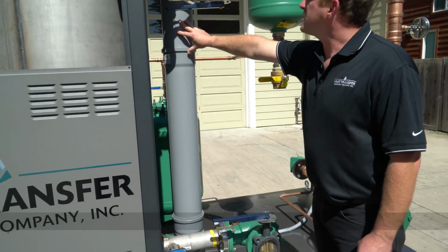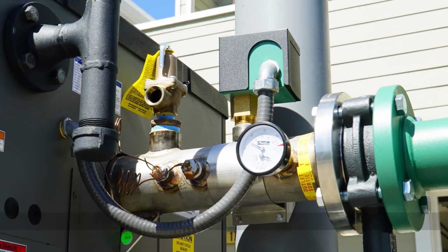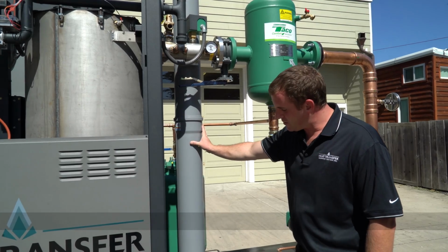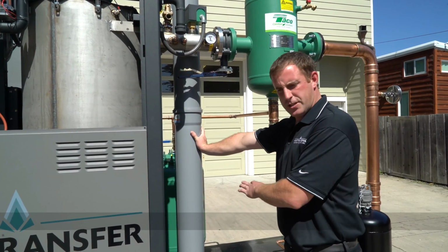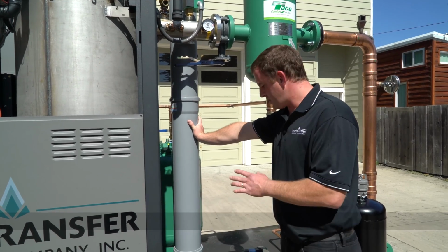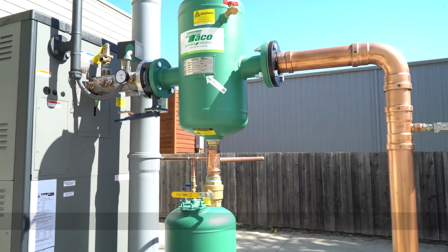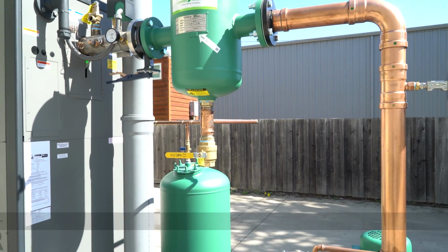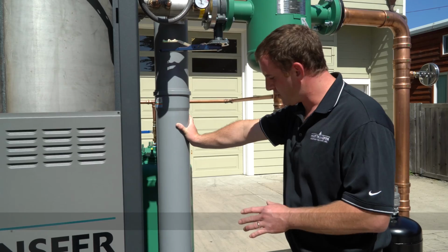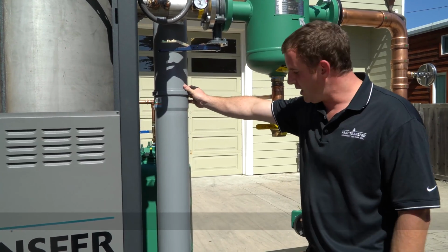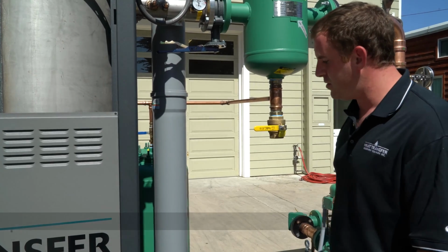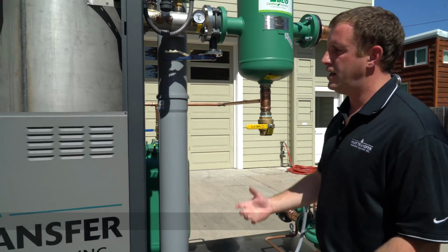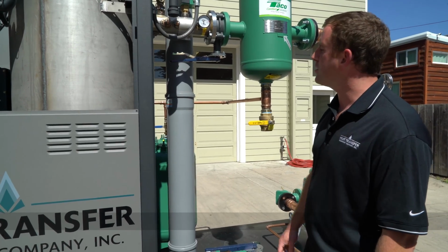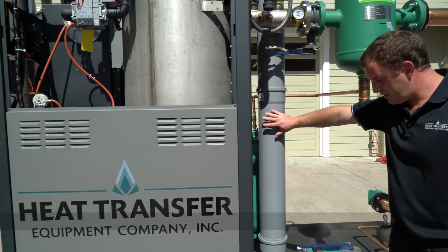On this particular boiler is Raypak's outdoor vent termination kit. It comes with polypropylene Centrotherm venting material, adapter piece, two 36-inch lengths, T termination, which we don't have mounted for shipping purposes. Built into this is a flue temperature sensor. When you start the boiler up, you have to program the flue material, and it will limit the boiler based on what the flue material selected is. Obviously, certain non-metallic venting materials like PVC or CPVC have lower temperature thresholds than metallic venting or polypropylene, which we have here. We're constantly monitoring the flue temperature through the Versa IC controller. It has logic within it to limit the high fire of the boiler should we start exceeding the temperature ratings of the selected flue material.